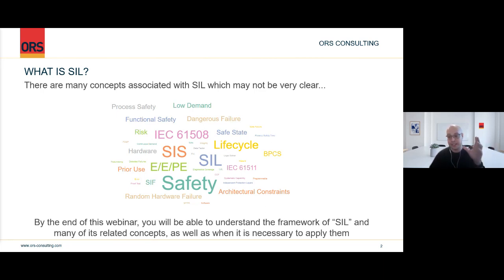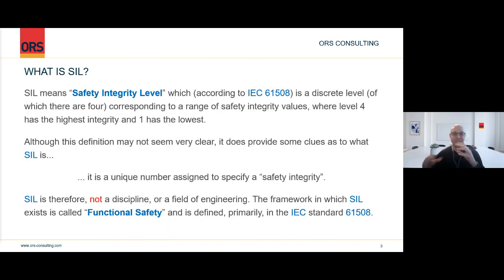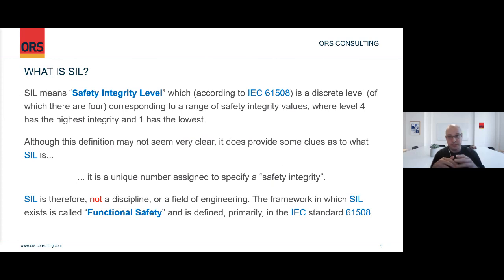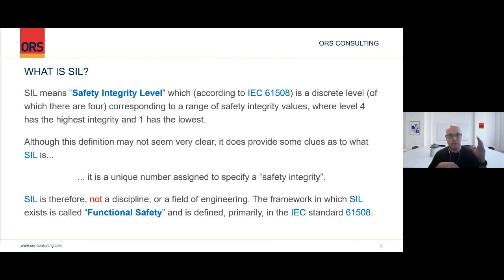SIL means the acronym Safety Integrity Level. SIL is defined in an international standard by the International Electrotechnical Commission — IEC 61508. SIL is a discrete level, of which there are four depending on the industry. For the process industries, we only have three, but as per IEC 61508, there are four levels of SIL, and it corresponds to safety integrity values, where level four is highest and level one is the lowest. It doesn't mean that four is better than one — it's just different safety integrity.